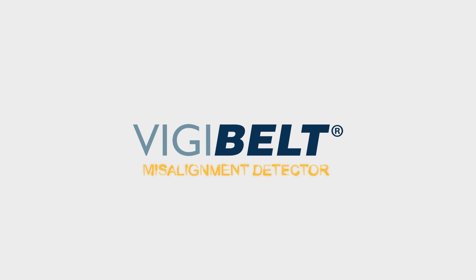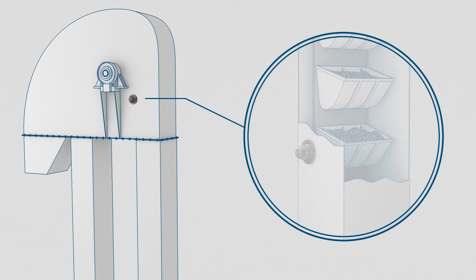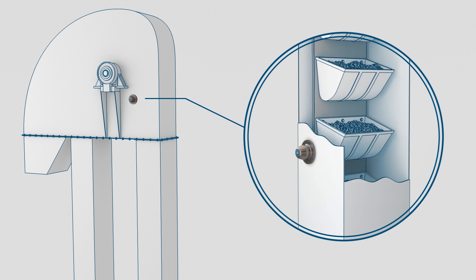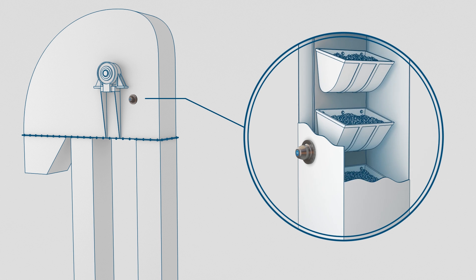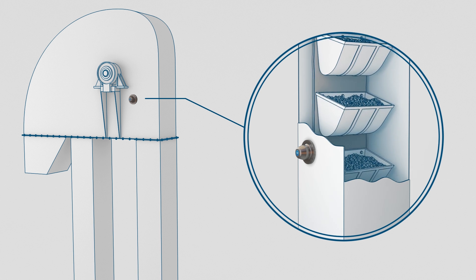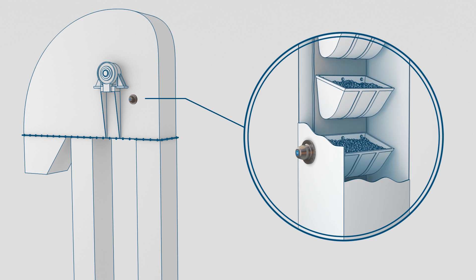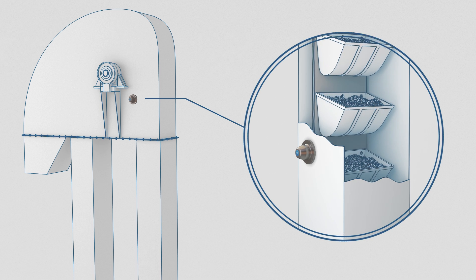VigiBelt Alignment Detector. Conveyor belt misalignment can cause the belt or buckets to rub or strike the elevator enclosure and produce heat or sparks. The VigiBelt Sensor monitors the conveyor belt for proper alignment. When the belt is misaligned, the sensor will alert the M-Jet Hazard Monitor and the M-Jet can stop the conveyor to prevent a source of ignition.